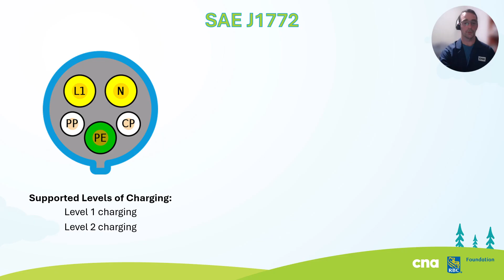It's going to supply AC voltage to our charge connector. Our N terminal, or L2 terminal, will act as a neutral when charging on level 1. But when charging on level 2, or connected to 240 volts AC, L1 is now 120 and neutral now becomes line 2, which supplies an additional 120, and we can get 240 volts AC now supplied to the vehicle's connector. The PE terminal is called protective earth, simply the ground.